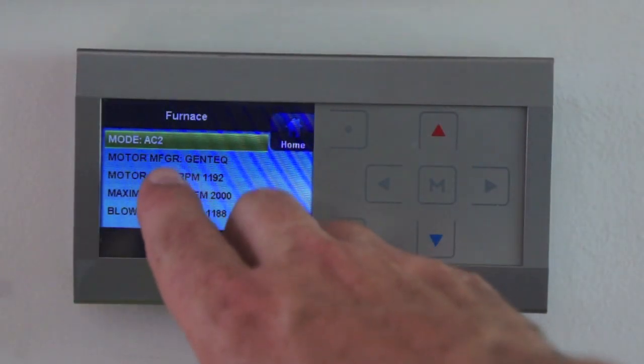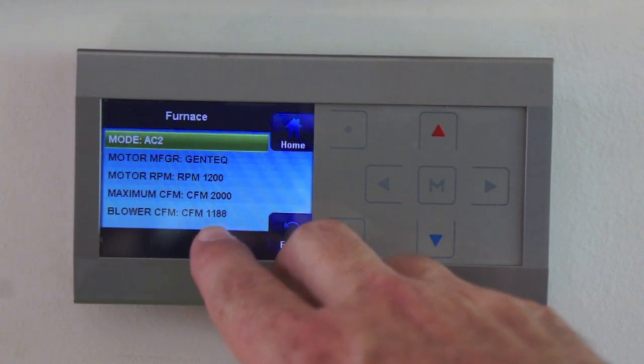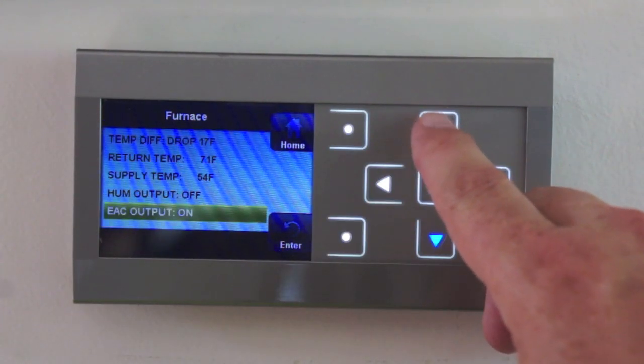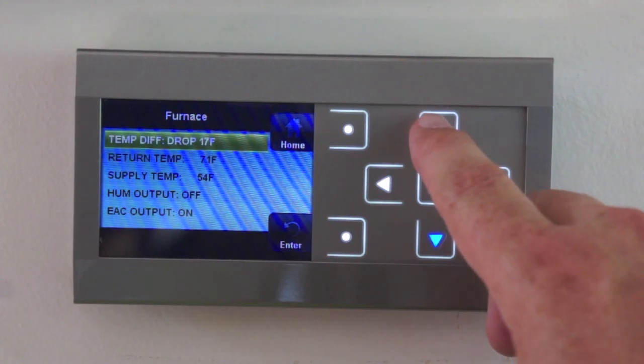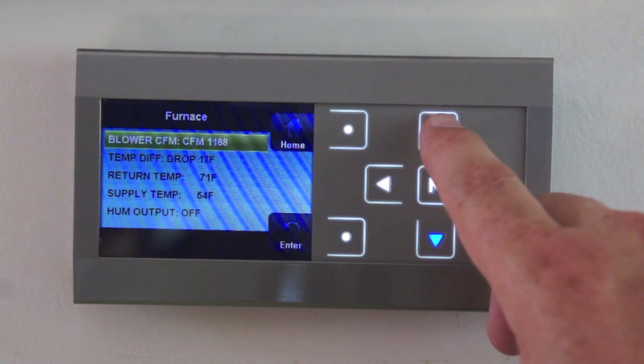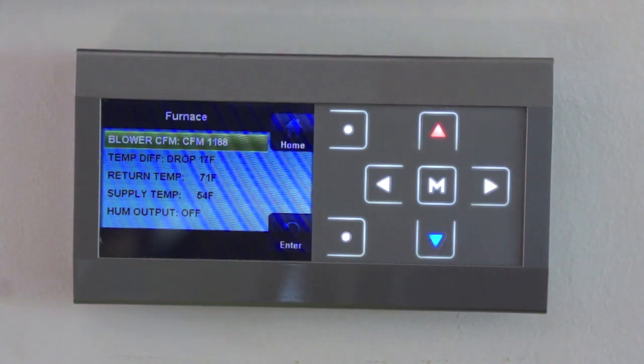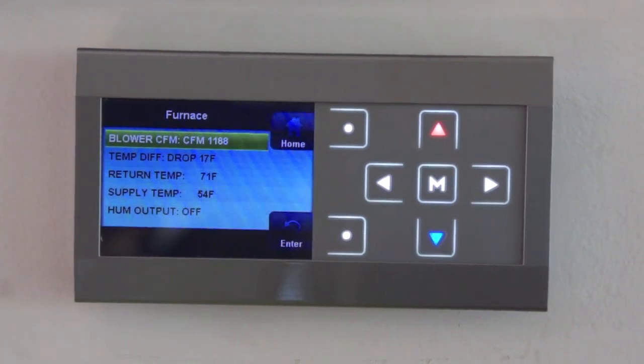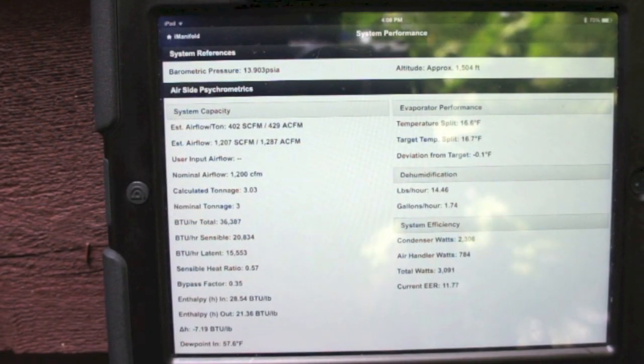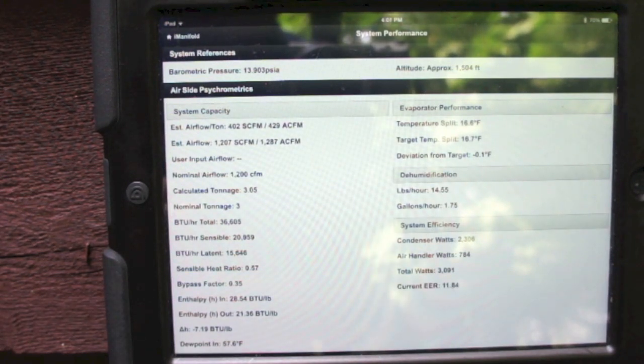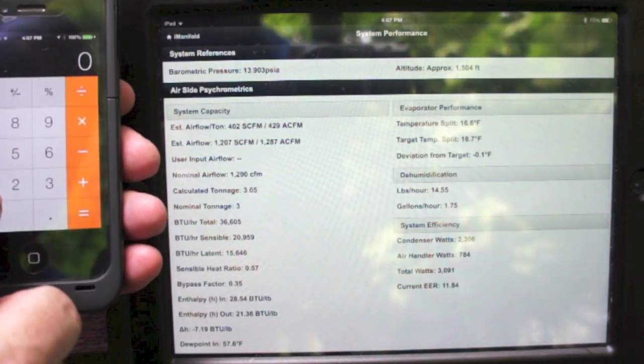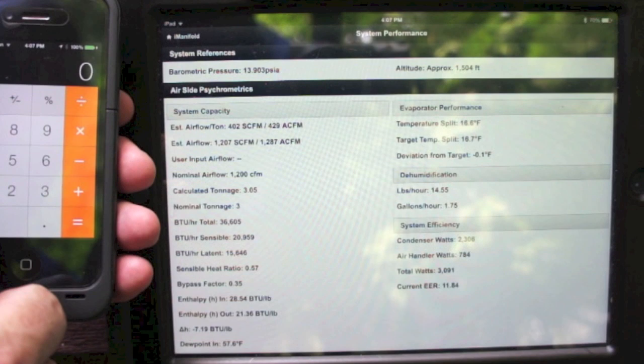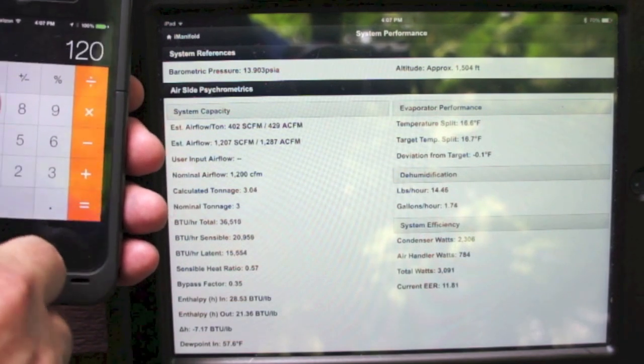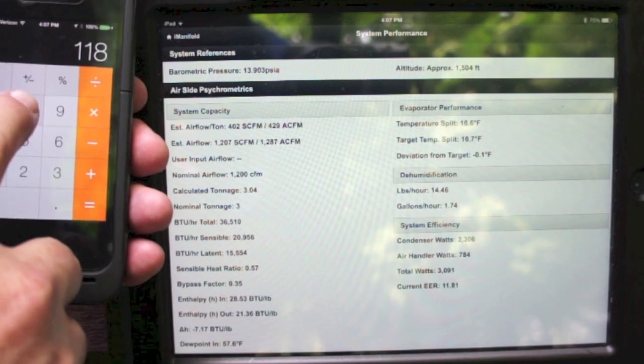Okay, so you can see now we're in second stage cooling. I'm moving 1188 CFM as far as my ECM is concerned, and my temperature split here, I'm going to scroll up here, we have a 17 degree drop across the evaporator coil, and again 1188 CFM. So we'll take a look at that compared to what the iManifold's calculating and see how we did. Alright, so we're back out here, and we're at 1188 CFM on the ECM. ECMs measure standard airflow, so let's go ahead and we'll calculate that out.